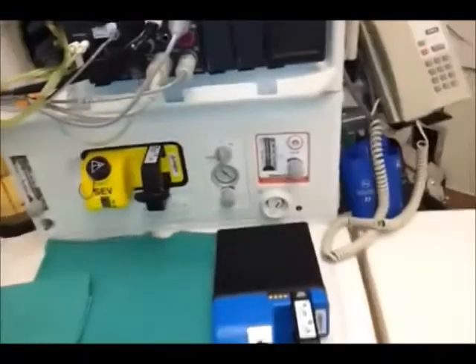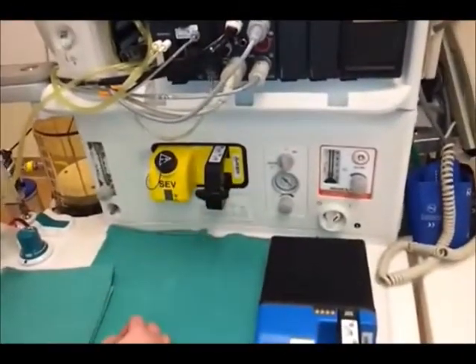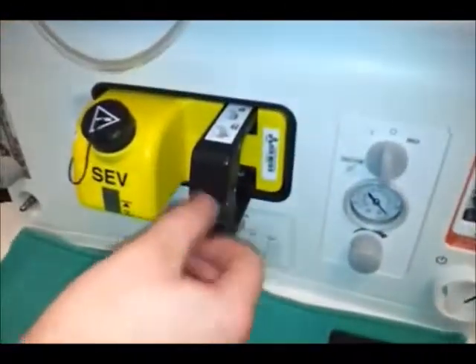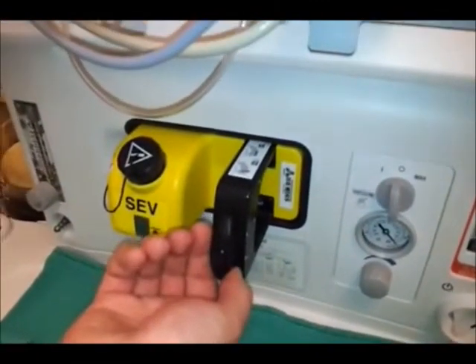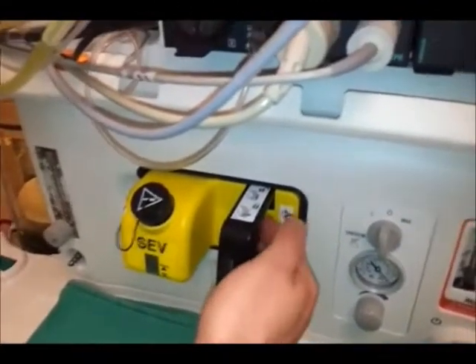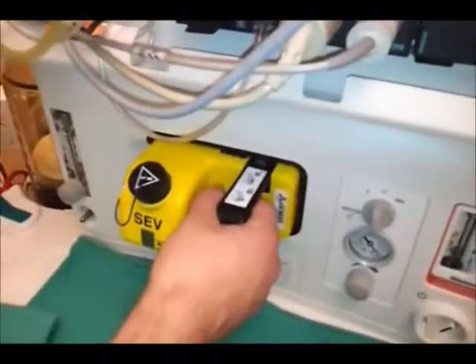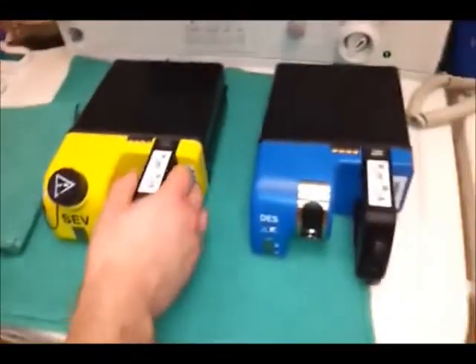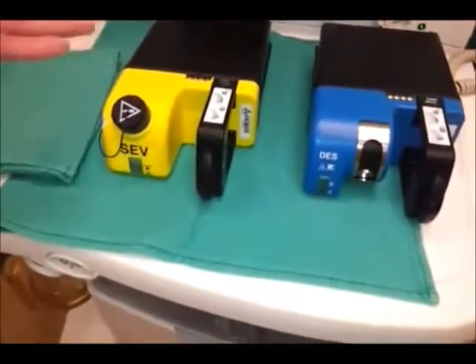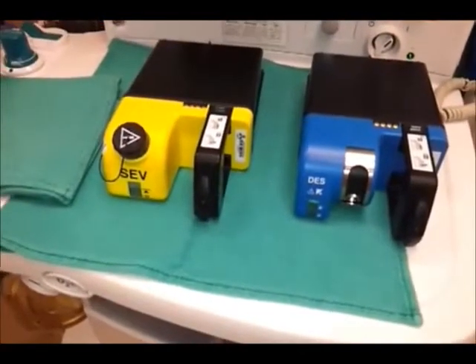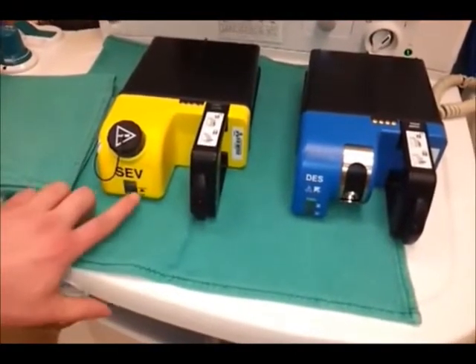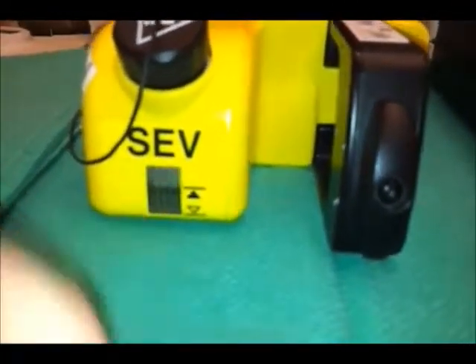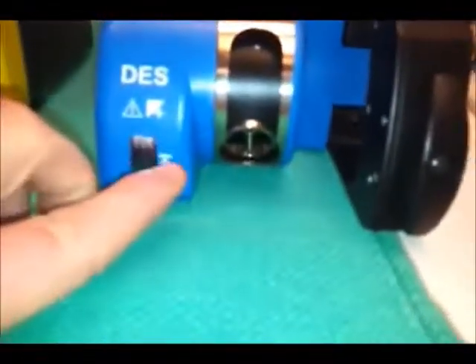The next thing you want to do is check your anesthetic gases. So you want to take them out. To take them out, you just turn this little lock here, and there's a little trigger in the back. You just pull the trigger and it pops out. So you want to set it on a flat surface to check the level, and to check the level you want to make sure that the gas is lined up with the top line here. You can see that on both of them.